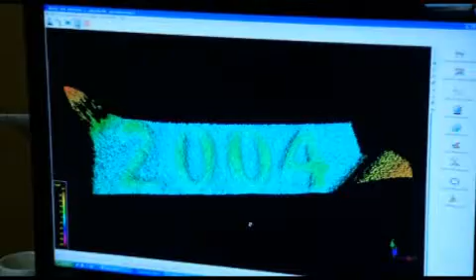Yes. Okay. This particular one, in some ways it's similar to what we saw with the OGP SmartScope systems that does an autofocus using contrast. The difference is with the OGP systems, we're doing the autofocus and acquiring a single data point using a very large number of pixels. Here, we're accumulating millions of data points through the field of view. So every one of those data points potentially has a different z-axis location. So the result of one scan in the z-axis is a topographical map similar to what you see over here on the screen. Okay. Now this is the year date of a dime, and it's been scanned with this, let's see, we used a 10x lens.